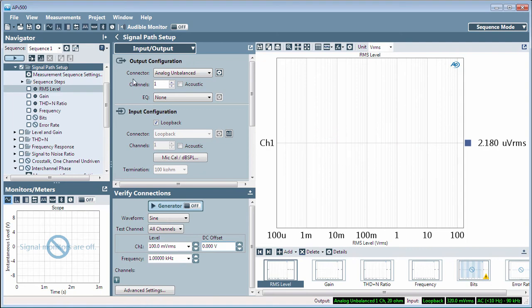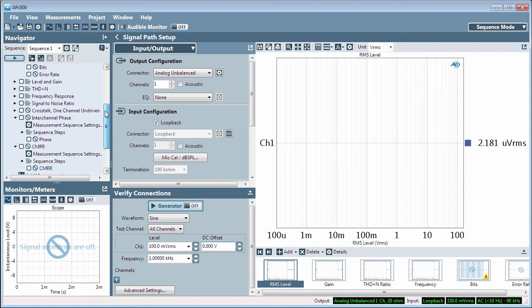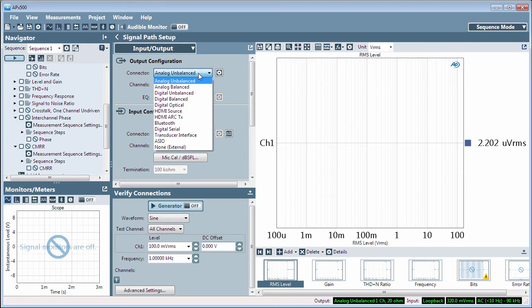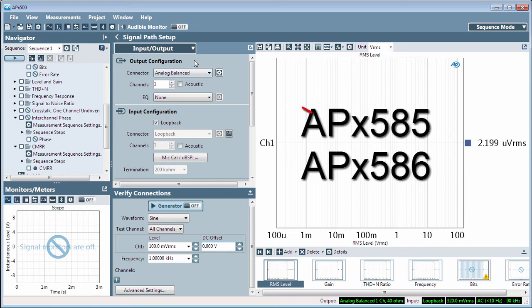In APX, the CMRR measurement is only available when using analog-balanced outputs, and it uses relay switching that's not available in the eight-channel output modules of the APX 585 or 586.